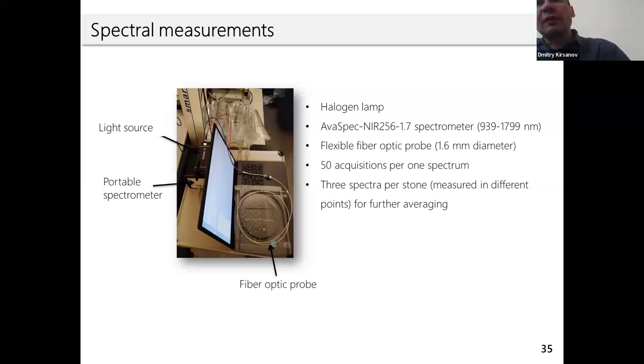You mean increasing the resolution, the spectral resolution? Yes, probably, but we have to check for each particular task. The main problem is not with spectral resolution, but that when measuring in saline, you're performing measurements in a flowing liquid, which flows between the detector head and the stone you need to measure. The spectra depend a lot on light scattering, and you need to find a proper point to minimize this flowing. Resolution can help, but in this particular case it's not the main issue.